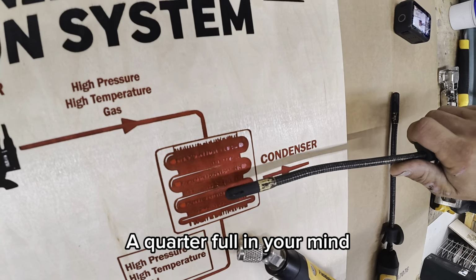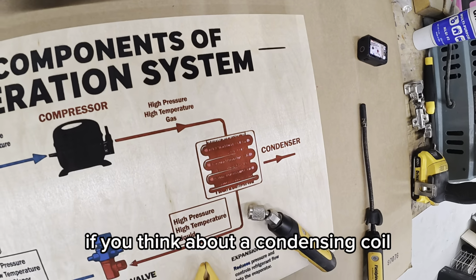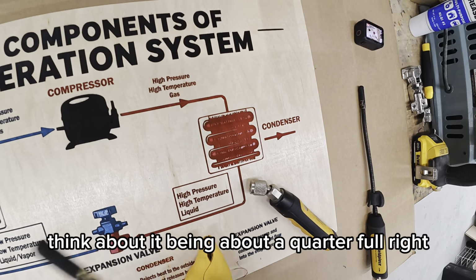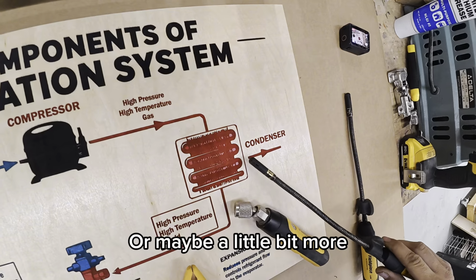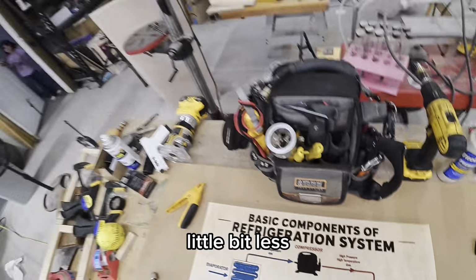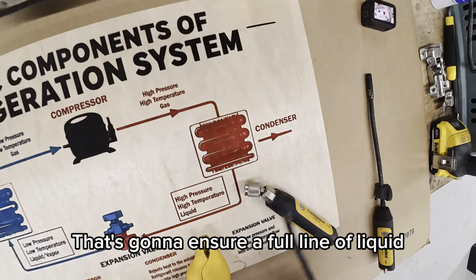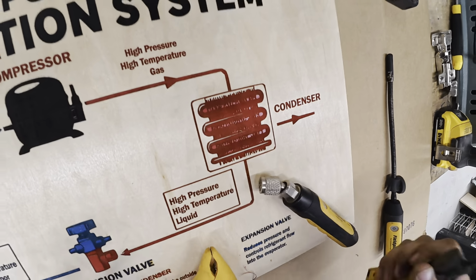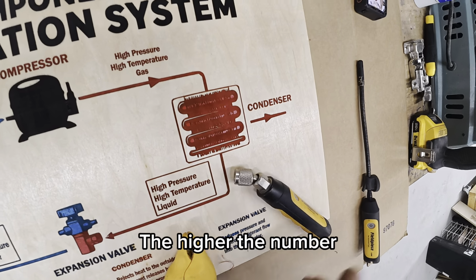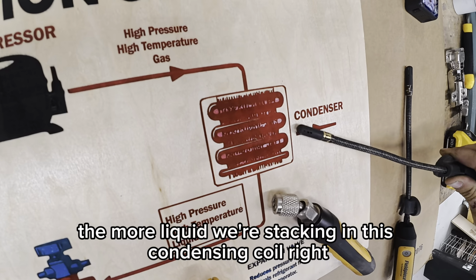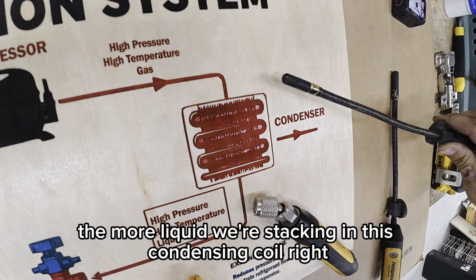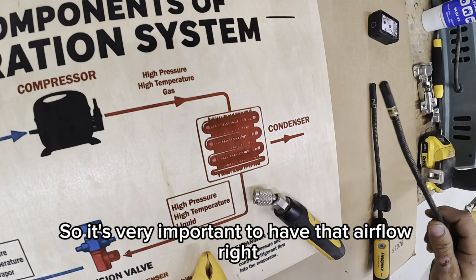We want about a quarter full in your mind. If you think about a condensing coil, think about it being about a quarter full, right? Or maybe a little bit more, a little bit less. That's going to ensure a full line of liquid, right? And that's what the subcooling number is, right? The higher the number, the more liquid we're stacking in this condensing coil, right? So it's very important to have that airflow, right?